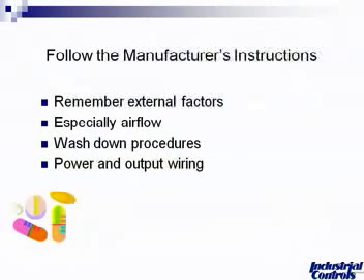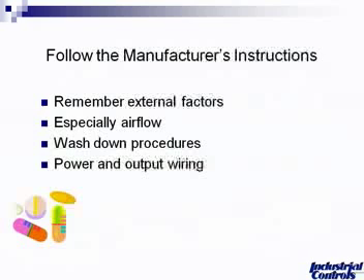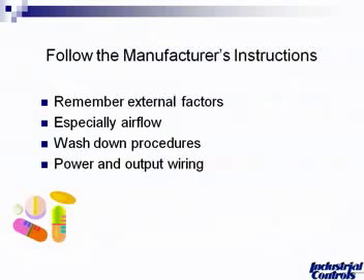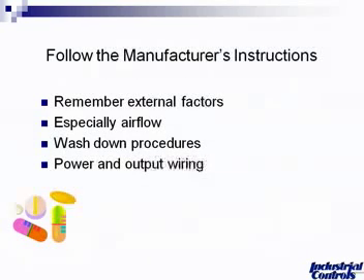Basically, you want to follow the manufacturer's instructions and remember all the external factors, most importantly temperature. You want to be aware of your humidity values, your temperature values, and what contaminants are present. Do you have air flow? In your wash-down procedures, how do you want to protect the sensor? Do you want to remove the sensor before wash-down? Do you want to cover it with a protective cap or filter?